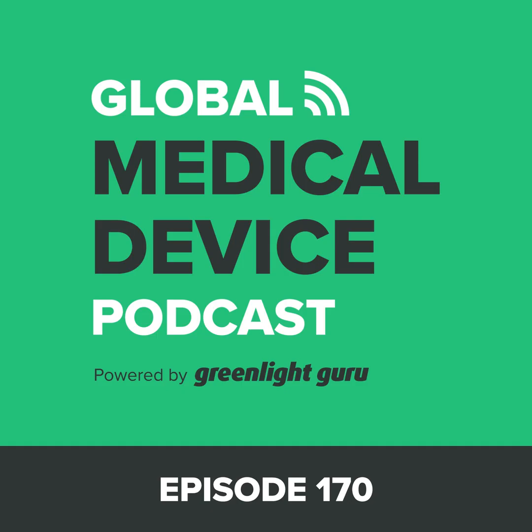Because to your point, this is the basis of everything that you're doing from a medical device perspective. This is what you claim your product is going to do. And what you claim your product is going to do is ultimately going to have an influence on how it's going to be classified. So it's really important to focus on that in every conversation that you have with FDA. Definitely. This intended use influences what clinical evidence you need to generate. It influences how you're going to be classified, what your regulatory path will be, what predicates you can use. It's really the linchpin for the whole thing.